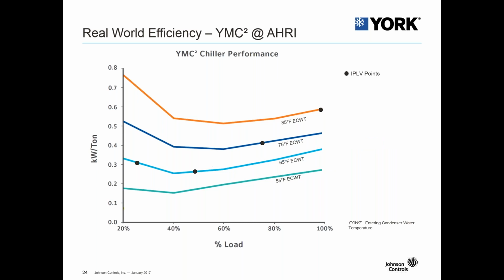real-world efficiency in terms of IPLV, what you'll see here are the 4 IPLV points that are used to create the single point metric that's often used to compare chiller efficiency. So each point is weighted differently. The 100% point at the design 85 entering condenser water temperature represents 1% of the total chiller efficiency for IPLV. And then there's the 75% point at 75 degrees, and then both the 50 and 25% points have 65 degrees entering condenser water temperature.